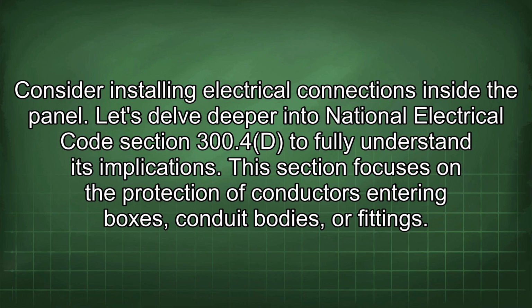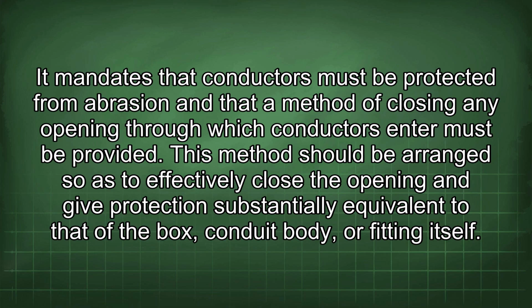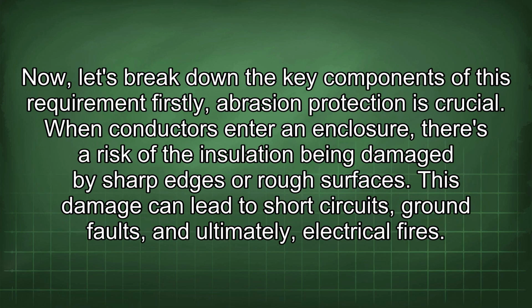Let's delve deeper into National Electrical Code Section 300.4D to fully understand its implications. This section focuses on the protection of conductors entering boxes, conduit bodies, or fittings. It mandates that conductors must be protected from abrasion and that a method of closing any opening through which conductors enter must be provided. This method should be arranged so as to effectively close the opening and give protection substantially equivalent to that of the box, conduit body, or fitting itself. Now let's break down the key components of this requirement.